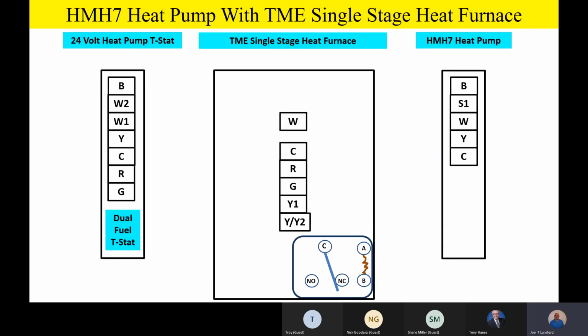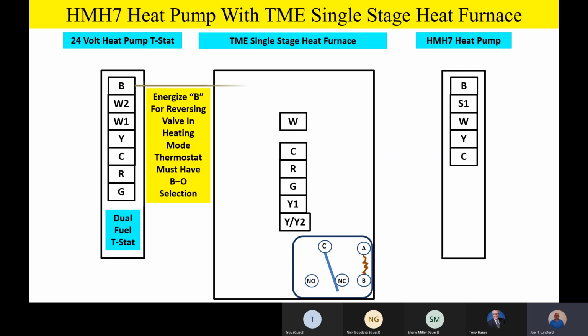As we take a look at it, there's that relay, and we're looking at a TME single stage furnace. This could be a TM9E or it could be a TM8E, either one. They use the same control board. And please remember, it has to be a dual fuel thermostat if you have it hooked up to a furnace. But just like before, B is going to go out from the thermostat right out to the outdoor unit. That's going to energize that reversing valve in the heating mode when we're in the heat pump mode.